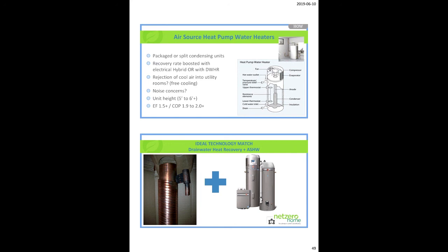Now the new systems come with a duct kit, so when it uses the air out of the room to heat the water, it rejects the cold air. You can either do it back outside, or - what we have in a couple of projects we've done - we put it back into the forced air system, which is really cool. We found it has negligible effect on the heating and comfort levels of the house at all, but in the summer, when we take showers in the morning, we get free cooling.